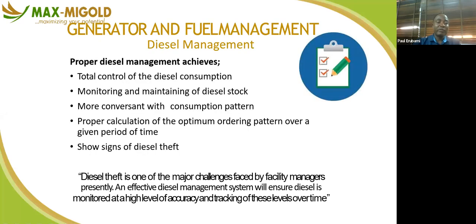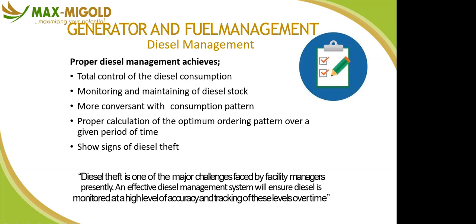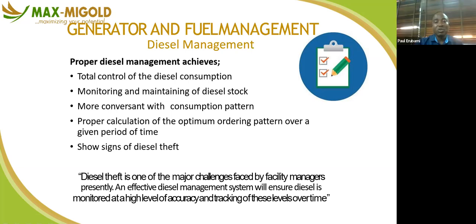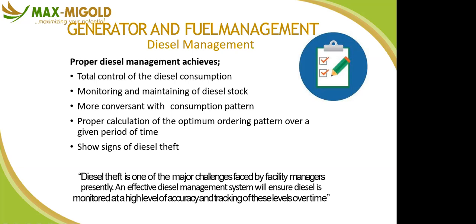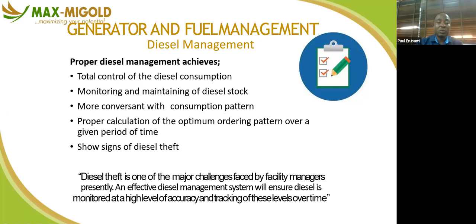So, diesel management. Why do you have to manage your diesel? Because that is the food for the generator. If you do not manage your diesel appropriately, they will supply you adulterated diesel. You end up spending money to fix your generator where you could have avoided this. So there are things you carry out when taking diesel stock. When you do diesel monitoring, it helps you to establish a consumption pattern. You know how much a generator can consume at every percentage load. Generators are not loaded equally. There are peak loads, you know what you are consuming, you write it down. Off peak load, maybe weekends and night, you write it down.